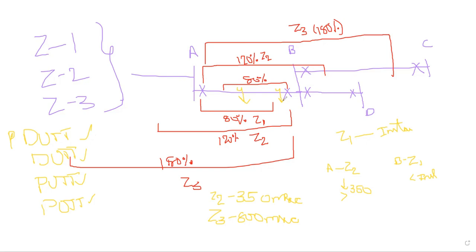These are related to the maloperation of the relays, because this relay maloperated and it again does this. But to get the confirmation and to make it a very reliable operation of the relay, these schemes we generally implement in our projects. One is the PUTT operation, the other one is the POTT operation. What is the PUTT? What is the POTT? PUTT is the permissive underreach transfer trip scheme.